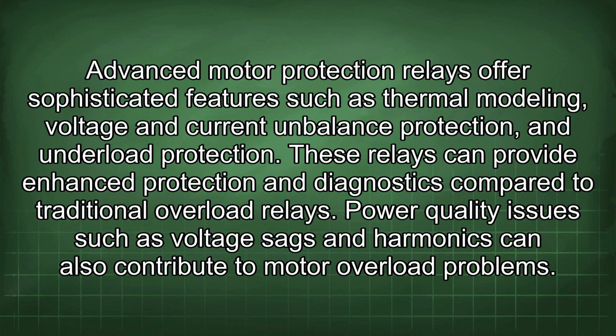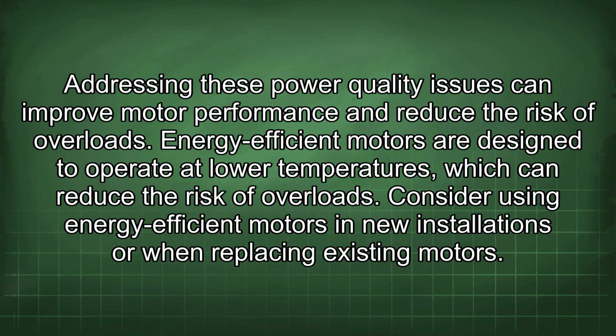Advanced motor protection relays offer sophisticated features such as thermal modeling, voltage and current imbalance protection, and underload protection. These relays can provide enhanced protection and diagnostics compared to traditional overload relays. Power quality issues such as voltage sags and harmonics can also contribute to motor overload problems. Addressing these power quality issues can improve motor performance and reduce the risk of overloads.